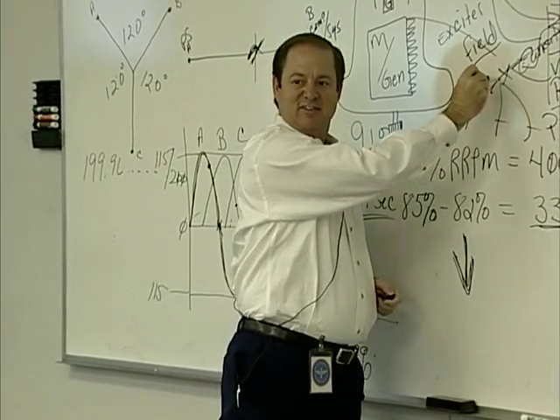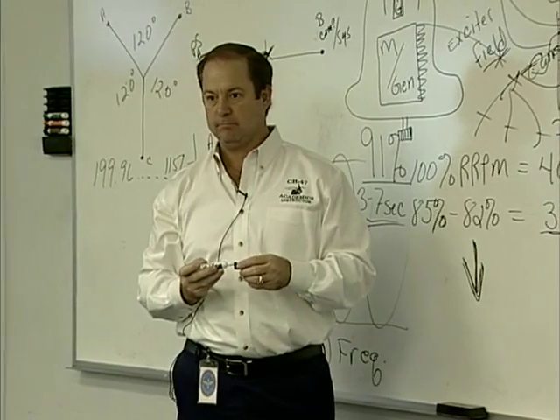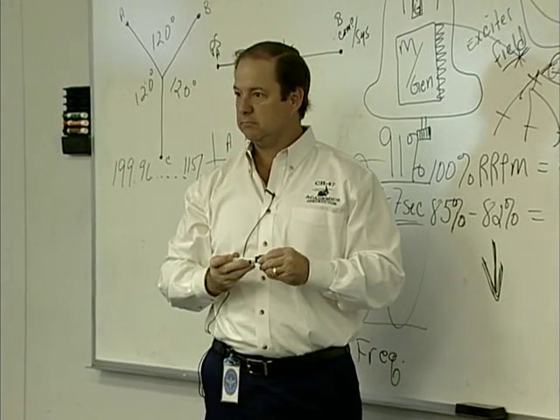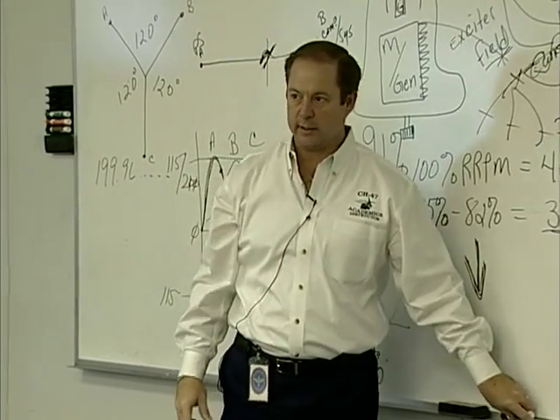If there's a major difference between what came out and what got to the power distribution panel, it senses it as a feeder fault, and so it will not produce your exciter field. Everyone tracking? Any questions about that?